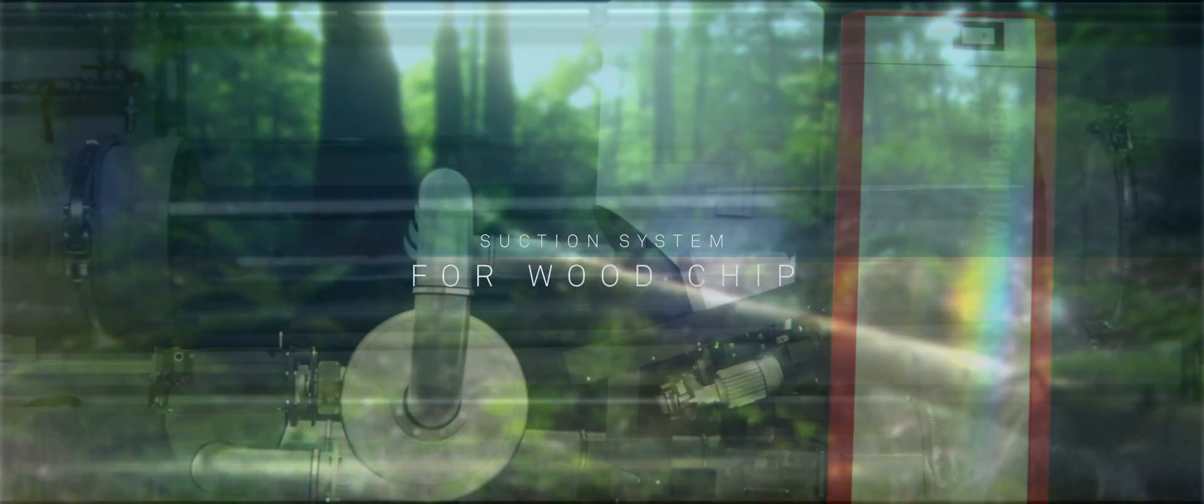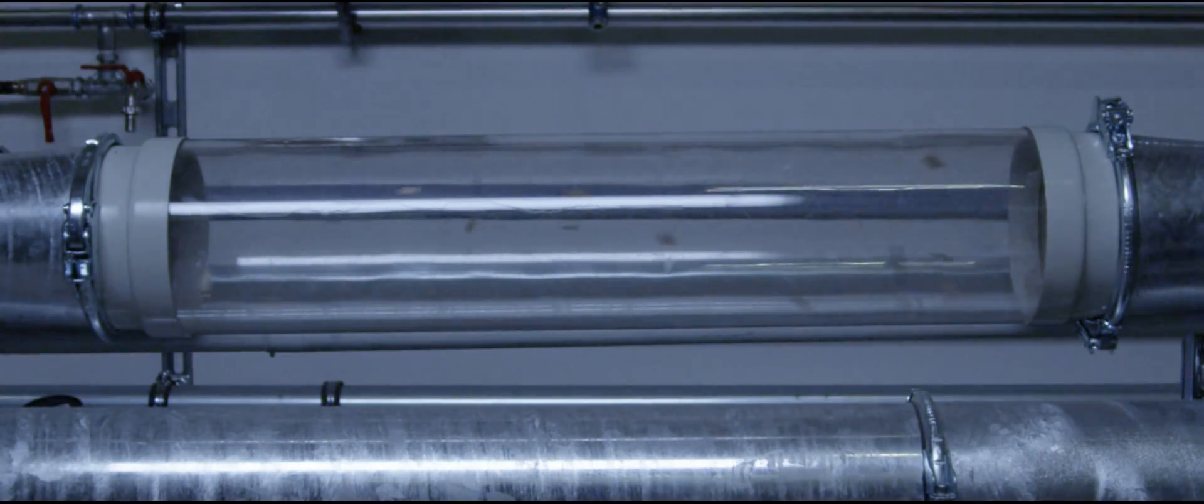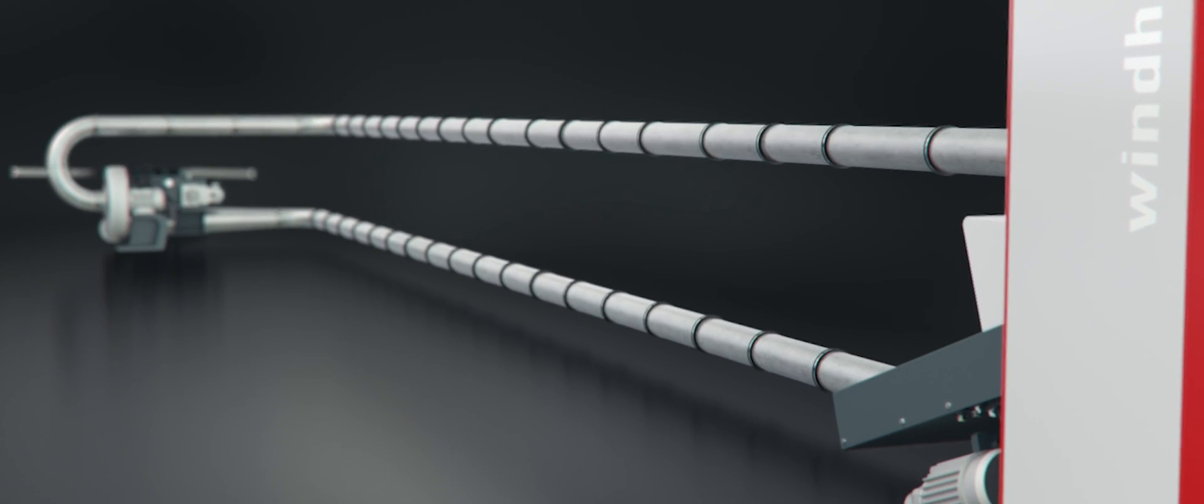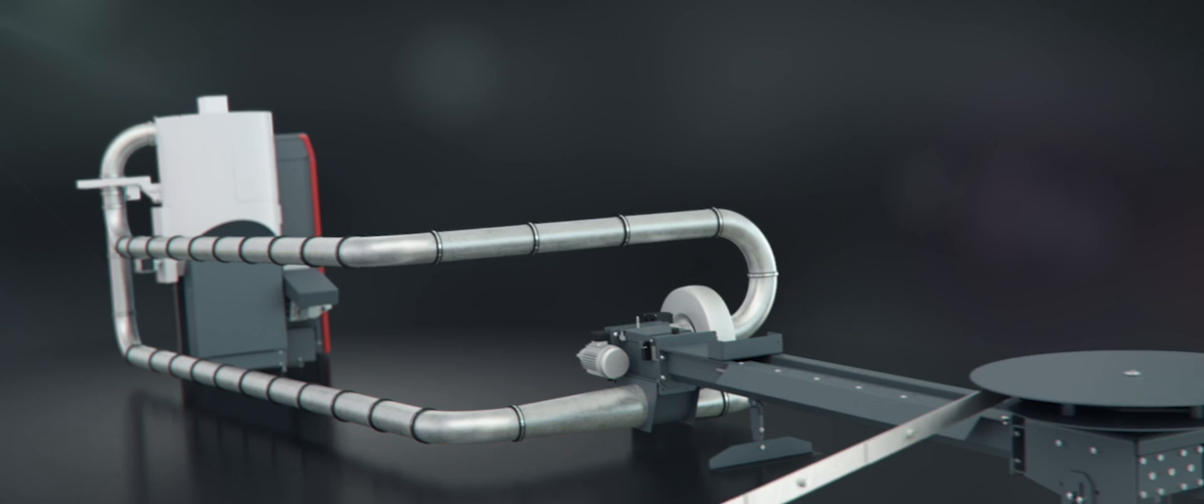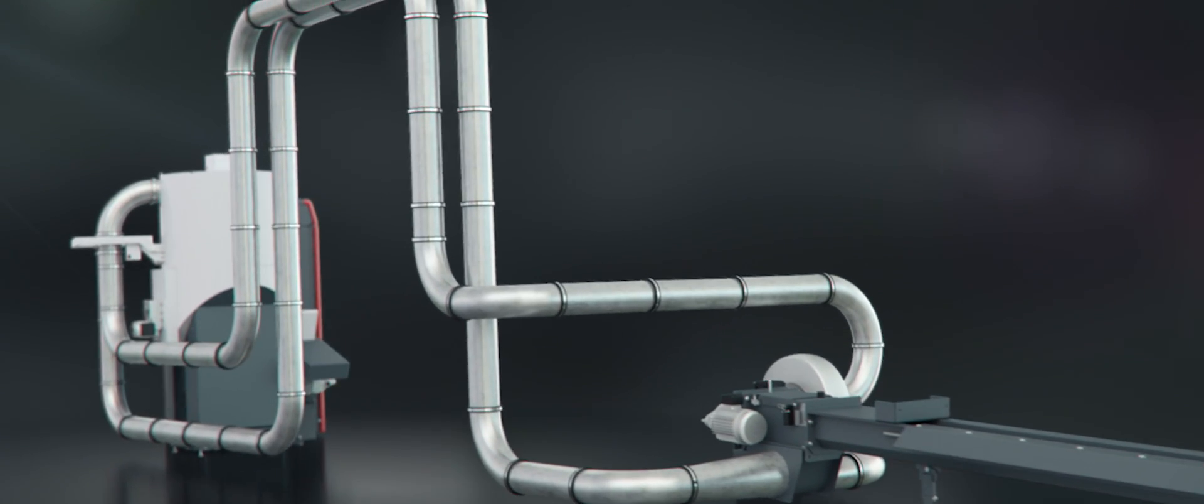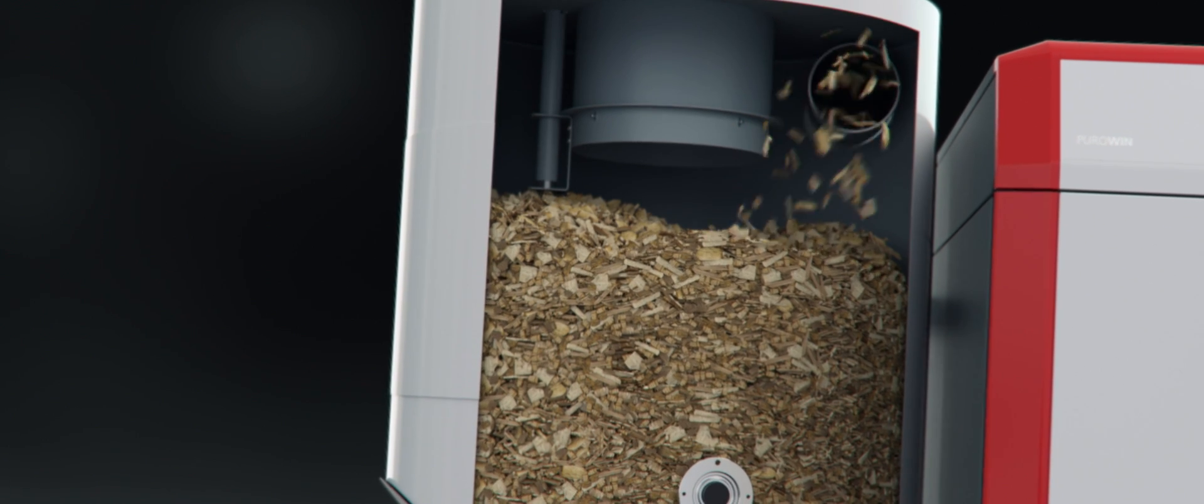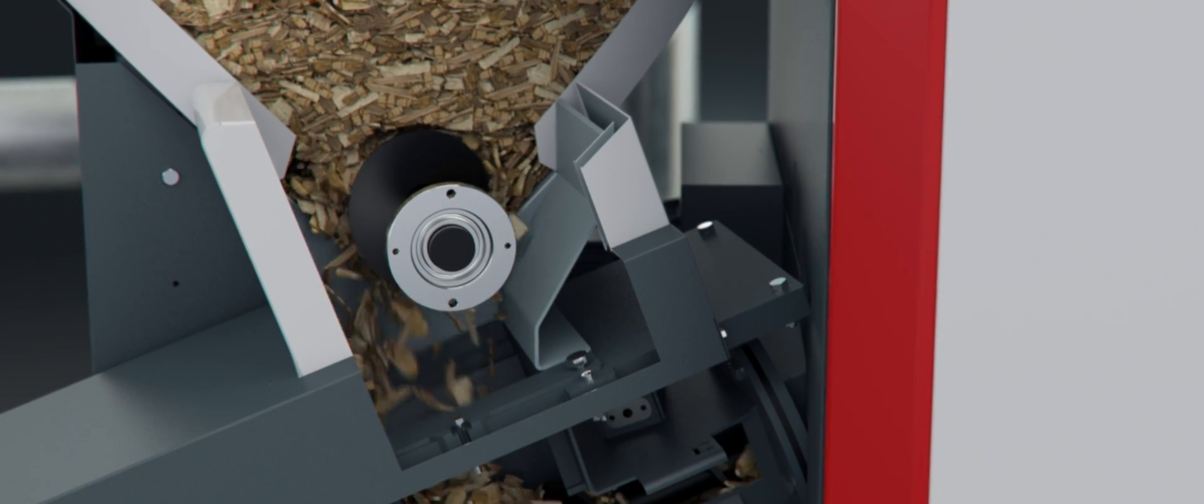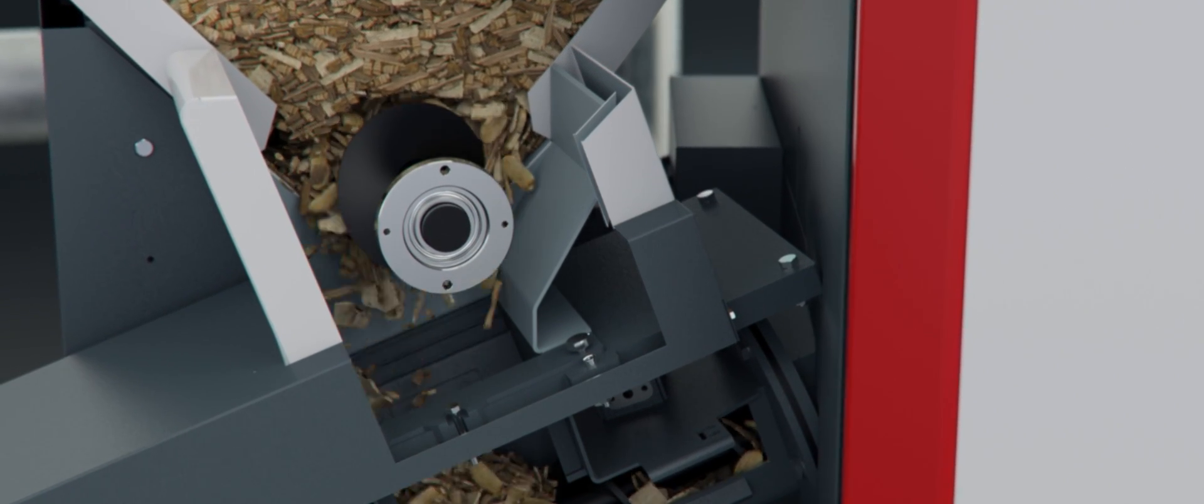We are redefining flexibility. The Puro win is the world's first boiler to use a suction extraction system for wood chip. The system can handle transport distances of up to 25 meters and heights of up to 7 meters and only runs for around 15 minutes a day. It's the ideal solution for anyone who has not been able to use wood chip because of the layout of their building.